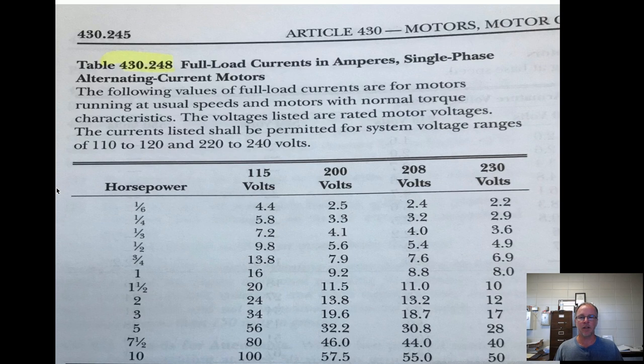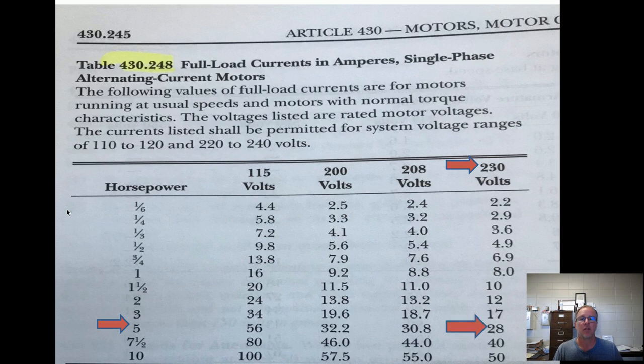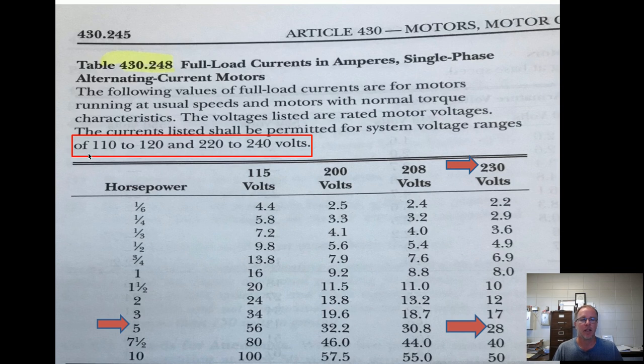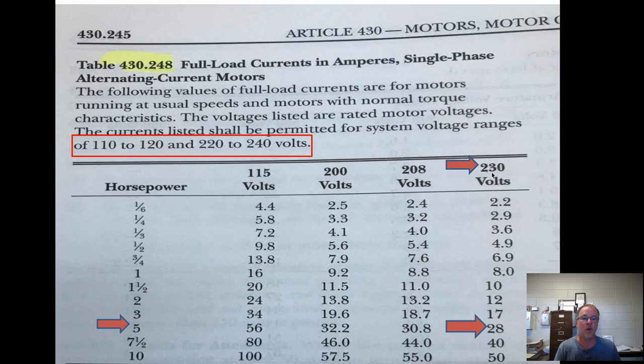This article right here shows the first question — five horsepower, you can see right down there with the red arrow. We're going to use the 230-volt column, so our answer should be 28 amps. One thing I want to show you: up there it says the voltage ranges from 110 to 120, or 220 to 240. So if the question says 220 volts, you look at the 230-volt column. Between 220 and 240, you use the 230-volt table.